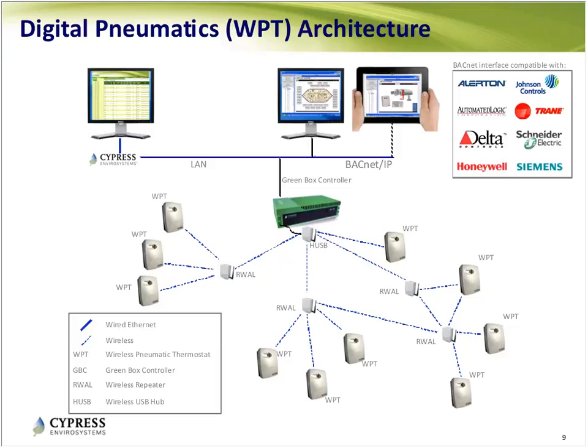If you have a high-rise building, usually we put one green box controller every 3 to 4 floors, and the repeaters can bridge through the floors. So again, it avoids the wiring, avoids a lot of the heavy expense with labor, just using wireless to transmit across floors to the green box controller.